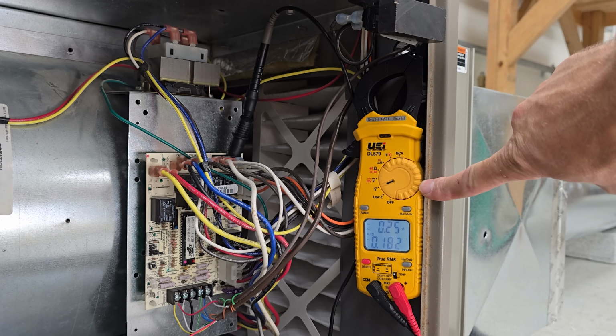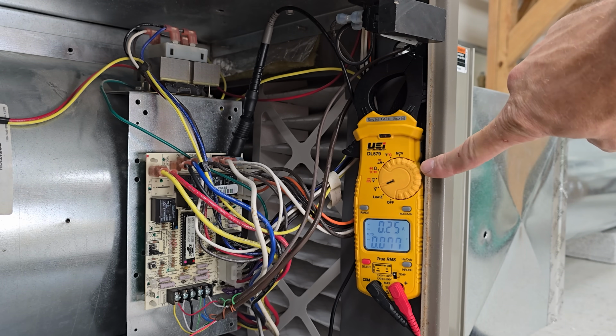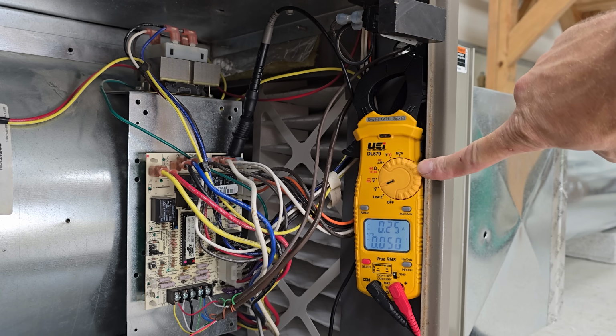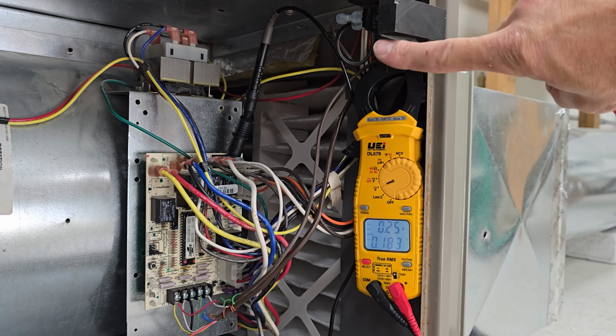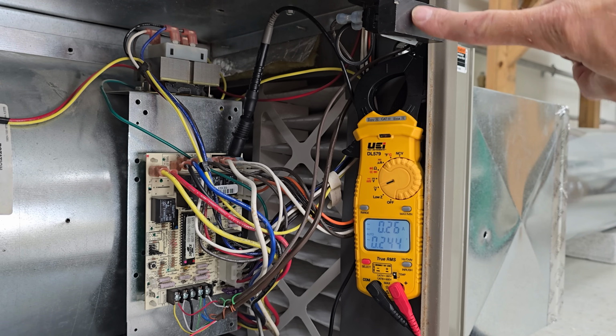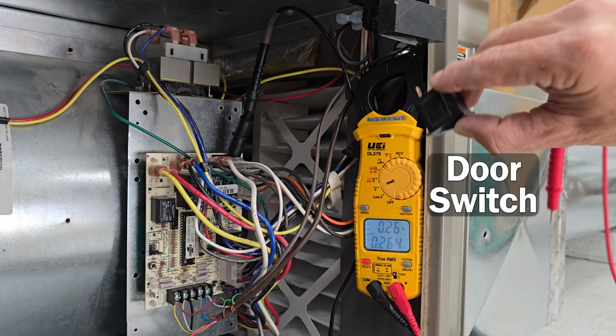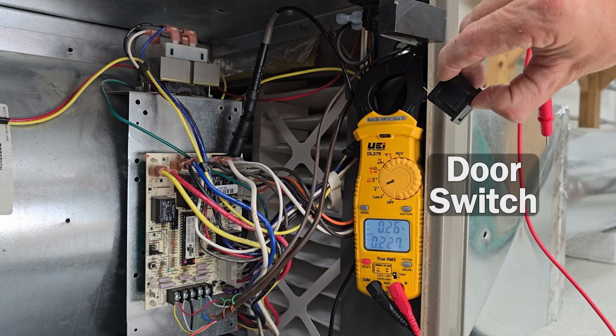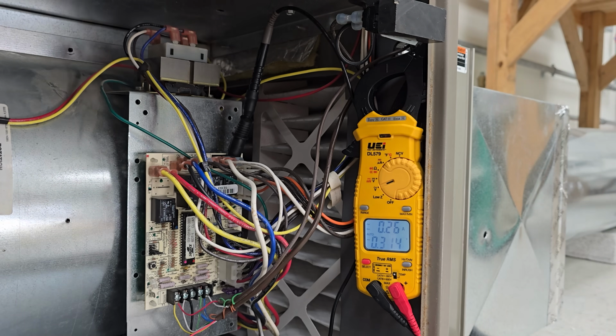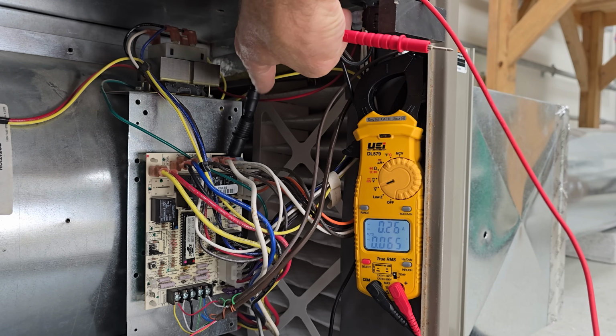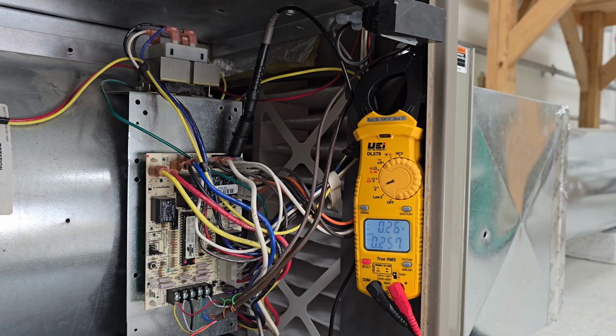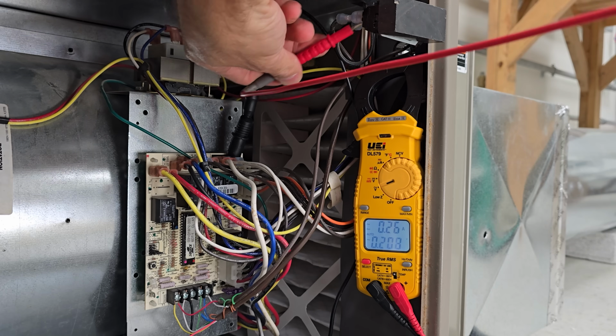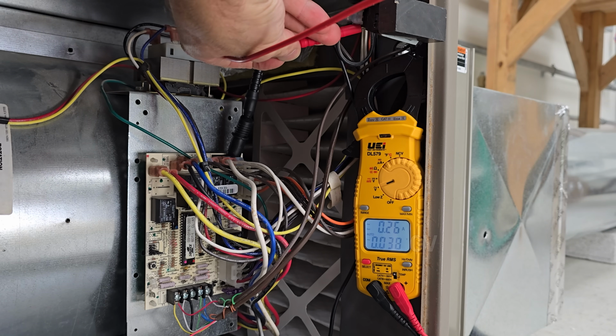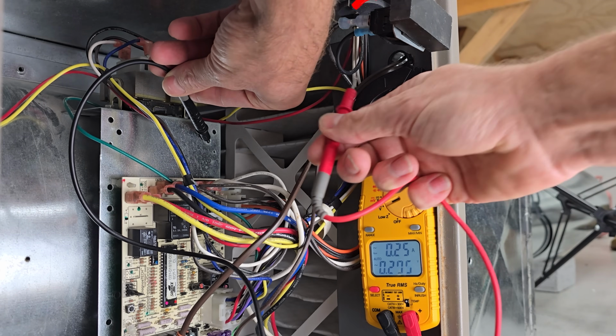So next we're going to use a multimeter. We have our multimeter turned on, and we have our display lit, and we're set to measure voltage for alternating current. We're going to be measuring for electrical power making it through this door switch. So we have the switch closed because we have a magnet in place. And this is what the door switch looks like. With it closed, we should have power being able to go through. We have one of our probes over here on the common neutral bar, and the other one we're going to place on one of the terminals of the switch between the spade connector and the switch itself. So we measure 0 volts there, and let's measure back here, and 0 volts there. So we don't even have power at this location.